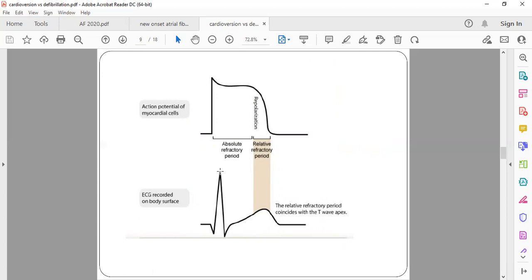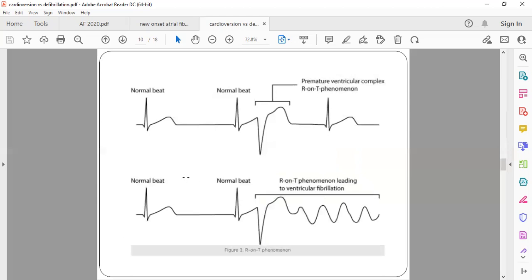If you give a shock at the T wave, the ventricle is already trying to relax, so delivering a shock then causes abnormal contraction without proper relaxation — this must be avoided. Delivering a shock at the peak of the T wave is called the R-on-T phenomenon, which can lead to ventricular premature contraction. This ventricular premature contraction can progress into ventricular fibrillation. That is why cardioversion has to be synchronized.